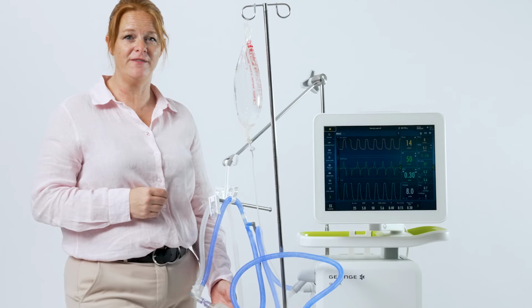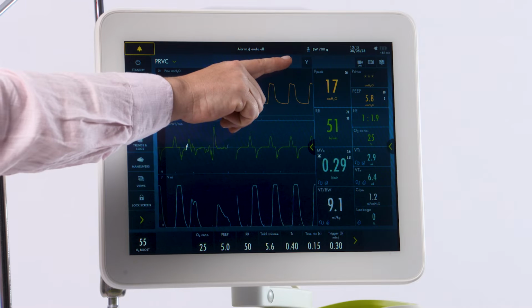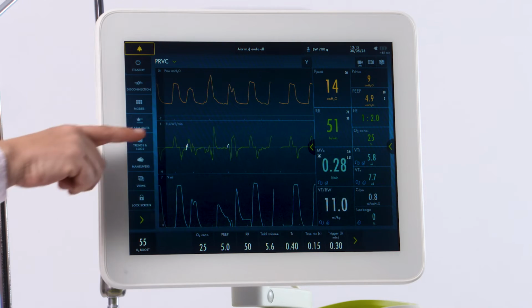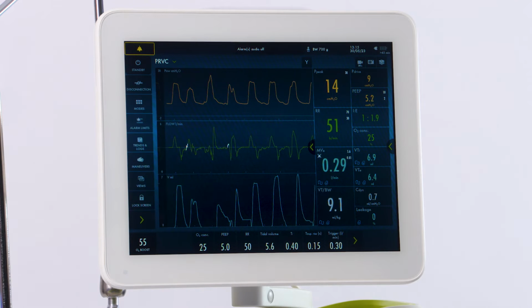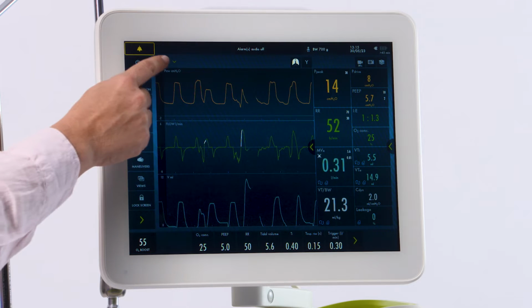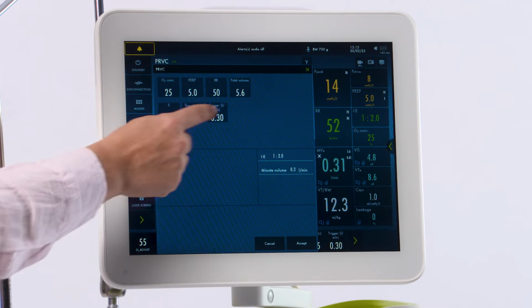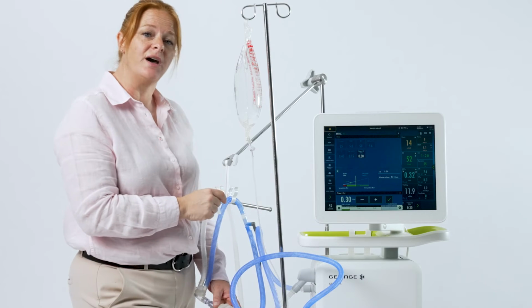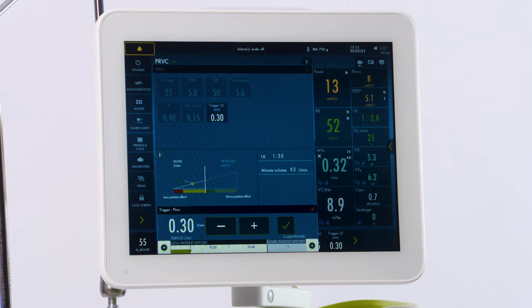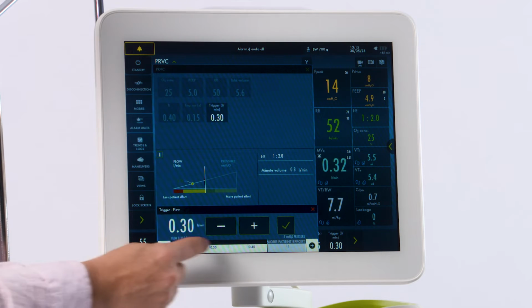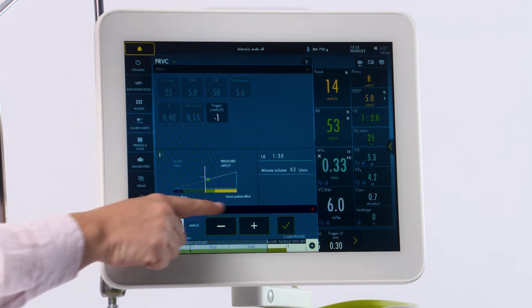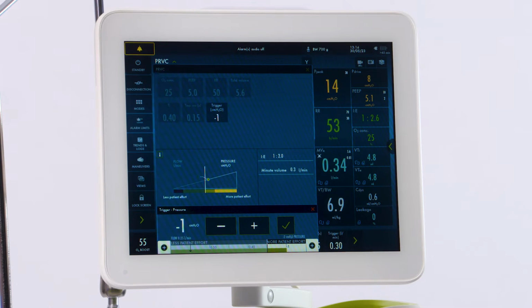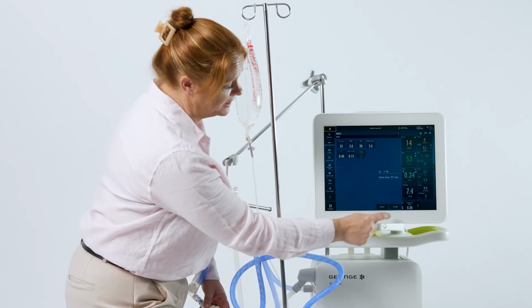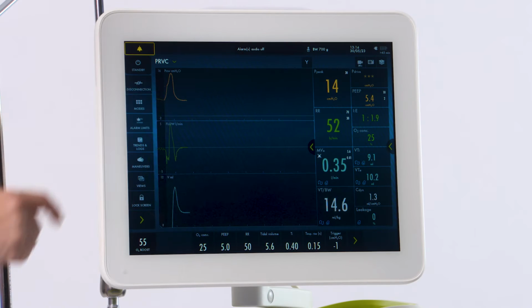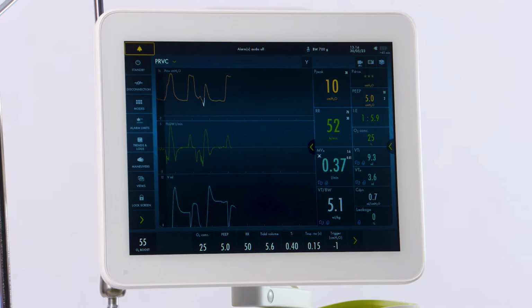To see your patient triggering the vent, it is indicated at the top with the lungs flashing. You will see a white mark on your flow scaler if it's set with a flow trigger. In order to adjust that to a pressure trigger, simply click on your mode and select Trigger. You'll notice a built-in tutorial is down at the bottom, currently with the flow trigger. If we move to the side, you will now notice a pressure trigger indicated here. If we accept this, you will notice my white now moves up to my pressure scaler.